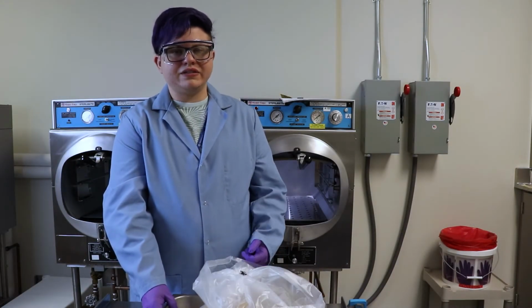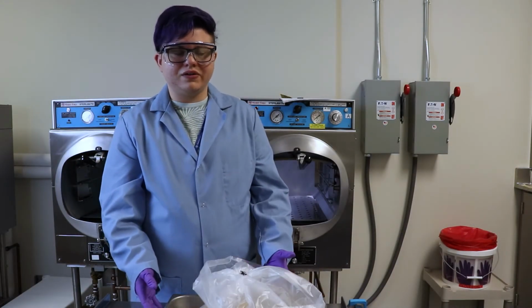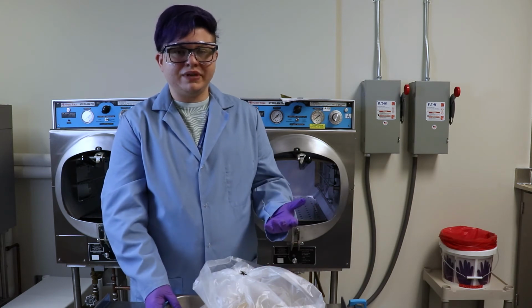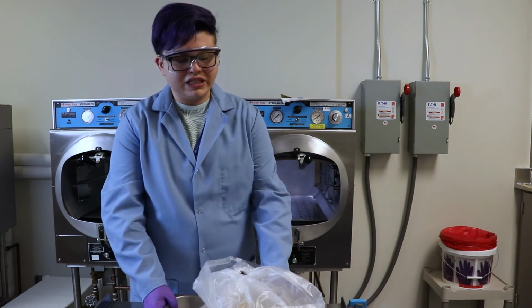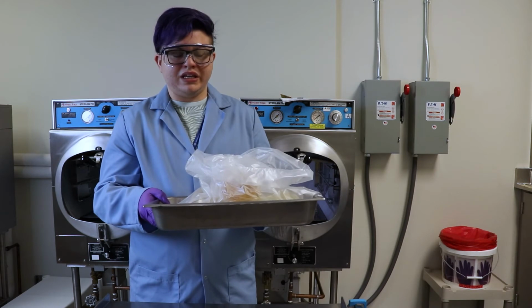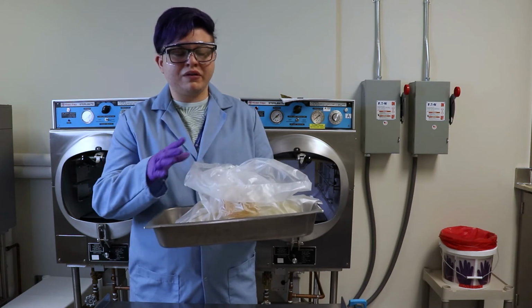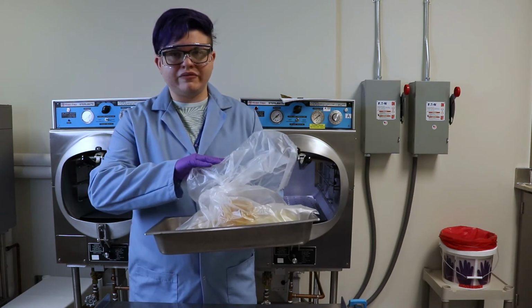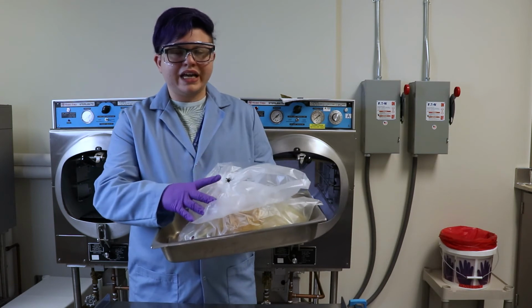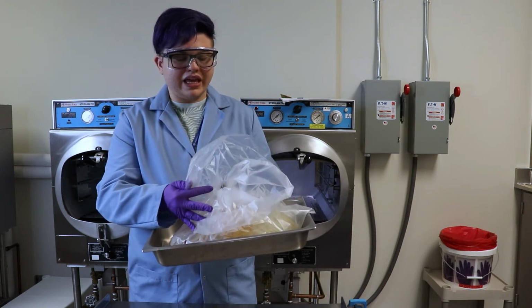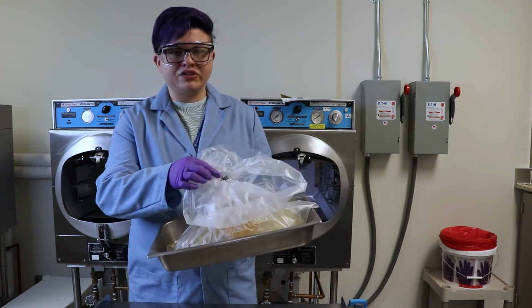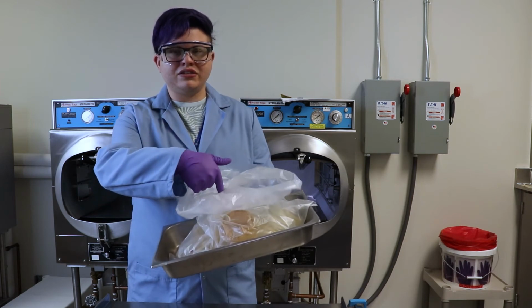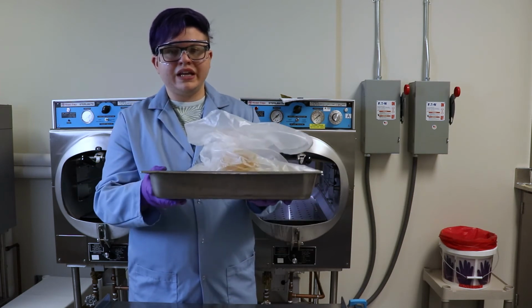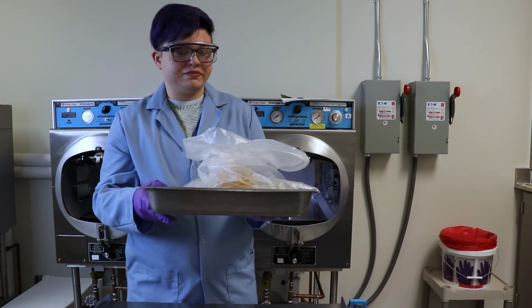The next step is to actually load the autoclave with the items to be decontaminated. When dealing with solid biohazard media, you want to make sure it is in a clear autoclave bag, tied loosely with a twist tie, enough to make sure that you can get a finger into the hole, and put it in a tray in case there is leakage.